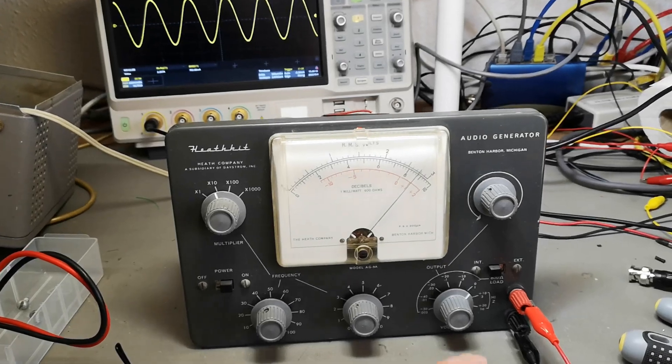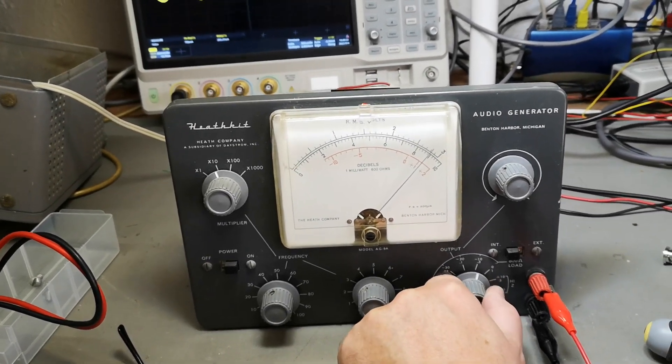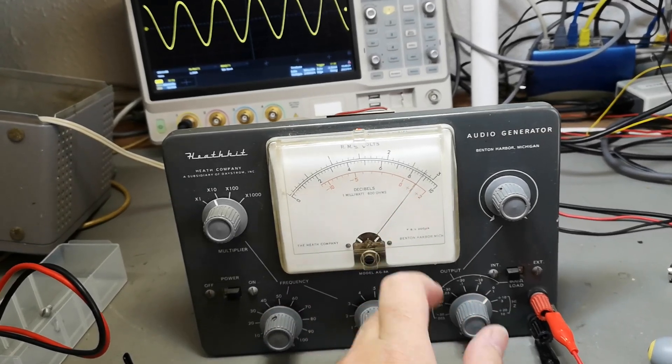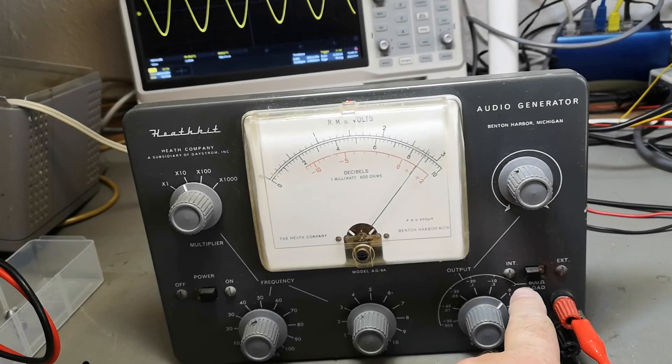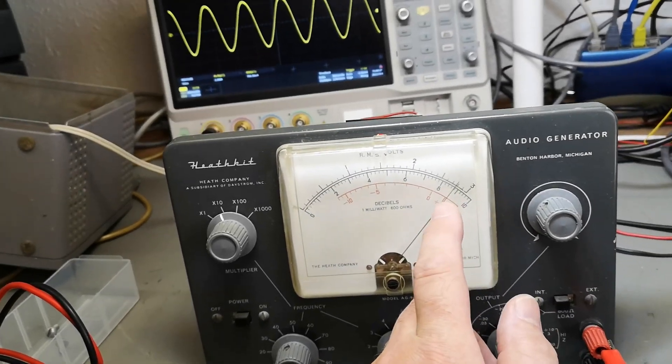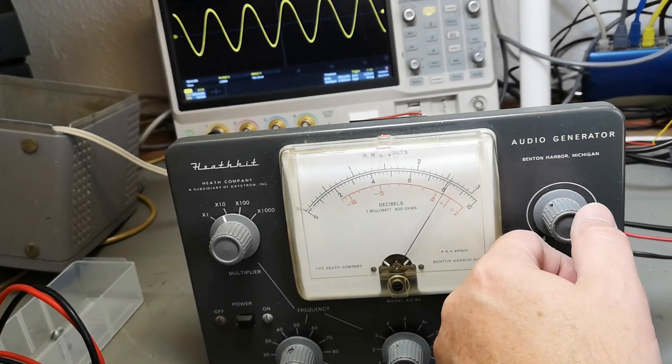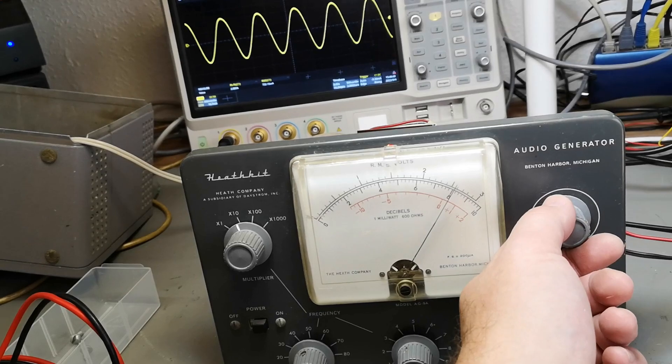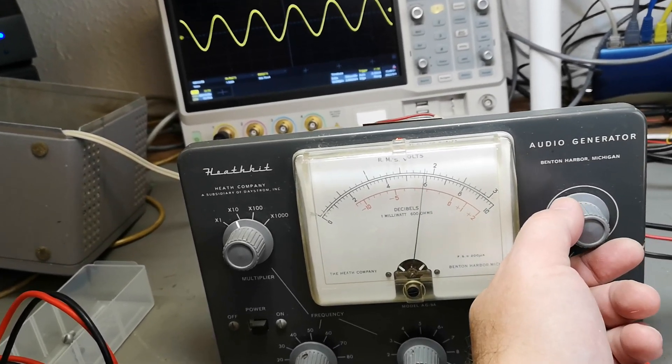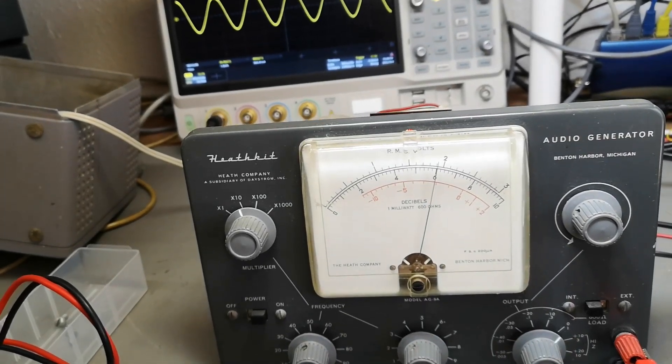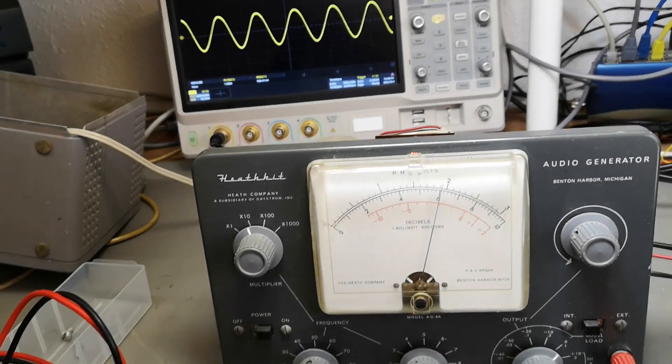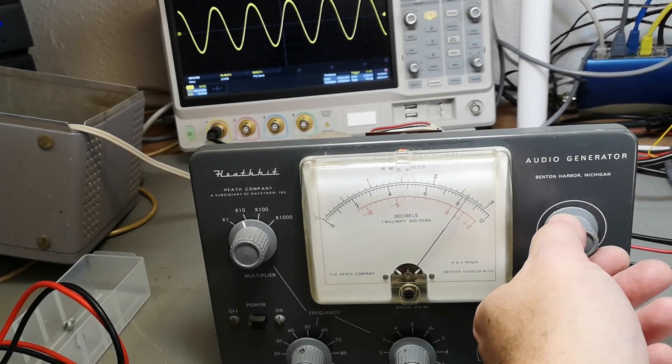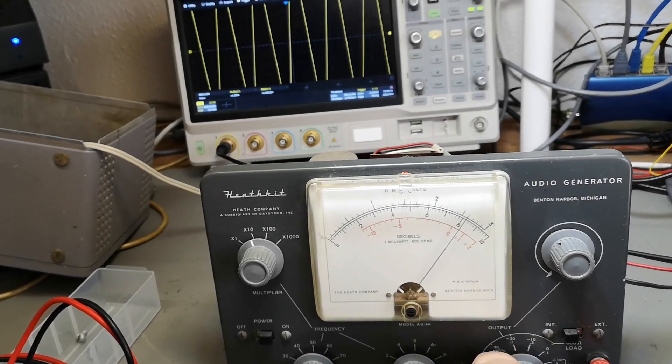What do you know, after a lot of cleaning and a lot of poking around with those switches, I got good output. It is reading a little bit low on the meter, so this should be one volt internal load. And what is that? So if I crank this down to 800 on the readout here, it says 730 on the scope. I mean, it's not really bad, right? So 600, and I read 550. I mean, it's not defect. I think it's possible to adjust this.